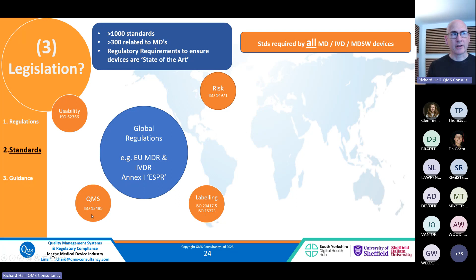Now, there are 5 standards which are going to be in every medical device. So usability, 62366, risk 14971, labeling has got 2 standards, and 13485 is the QMS standard for medical devices. Now, together with that, you get the majority of medical devices conforming to a lot of the other standards. So if you've got software in your medical device, then IEC 62304 is a standard to read to ensure that you meet that requirement. You must meet it before you go to market. If you connect that software to the internet, then 27001 gives you a basis for information security.